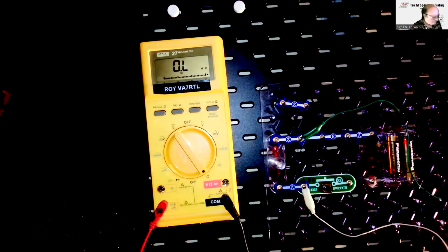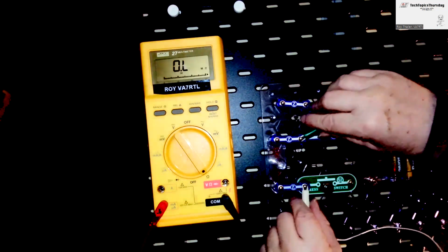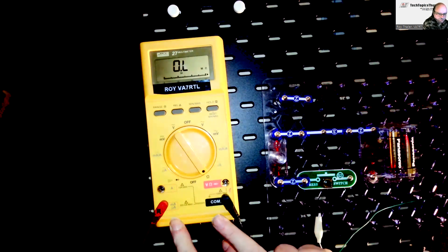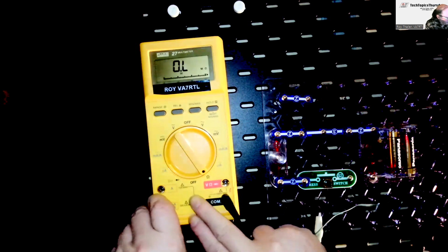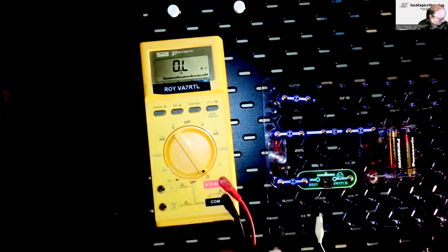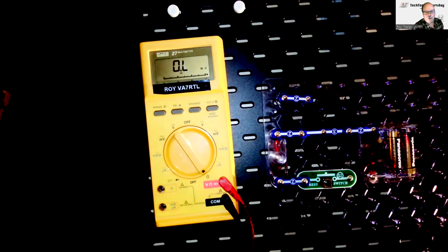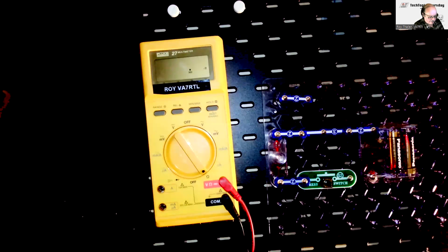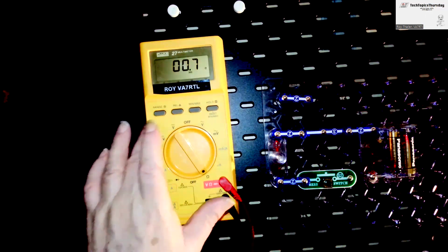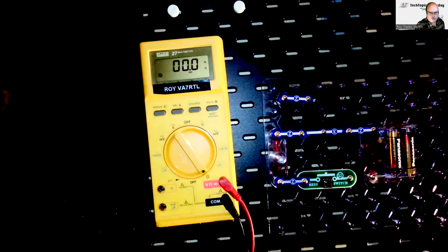When you have it set on the wrong range, like milliamps, it won't give you a reading. You need to make sure it's set on the right one, and then it'll give some indication, like OL, along with a bar graph. If I put these two leads together, it tells me this is 0.8 ohms. If I want to null out that 0.8 ohms, I just press the relative button up here, and it zeroes it out.